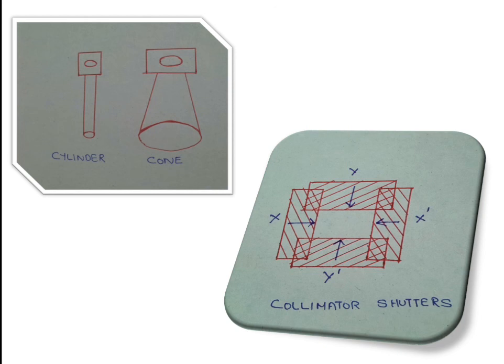The collimator shutters can be brought close together or set apart to determine the area of exposure. Inside the collimator there is a collimation light — switching it on shows how much area will be covered by radiation. If the area is too large, we reduce it by bringing the shutters closer: bringing Y and Y-dash closer, and X and X-dash closer, to adjust the exposure area as needed.